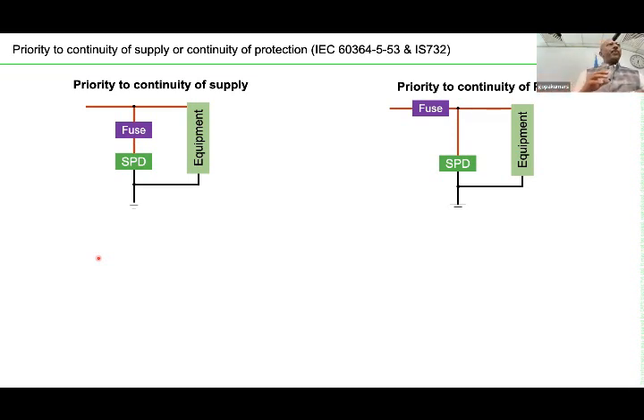So one of the important subjects of SPD is its backup protection. Backup protection, in the sense, as I said, the SPD is supposed to create a short circuit internally, especially the MOV. Then internally it has a thermal isolator. Probably that will work. But if the thermal isolator doesn't work, what will happen? It's a short circuit. Your building will have a problem.